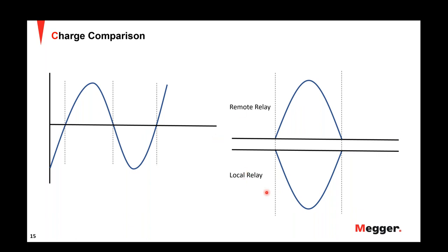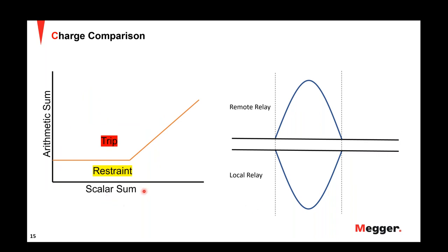So once both the relays receive all the information, the local and the remote relay current magnitudes are used to calculate the restraint quantity and operating quantity. So basically, the restraint quantity is gotten by performing a scalar sum, which is the sum of absolute magnitudes of those currents. And then the operating quantity is gotten by performing the arithmetic sum, which would be the absolute magnitude of the sum of signed magnitudes. So now here is my operate quantity and restraint quantity.